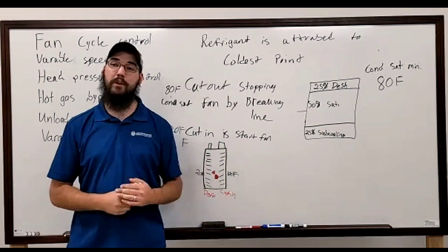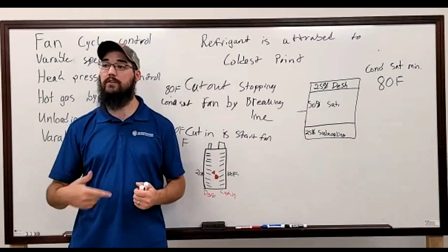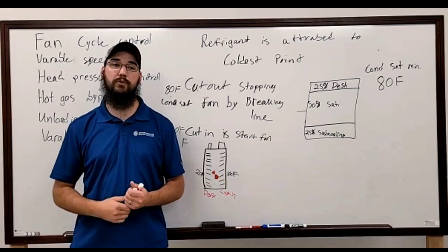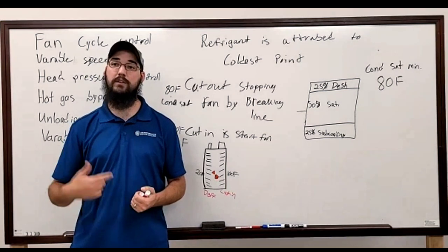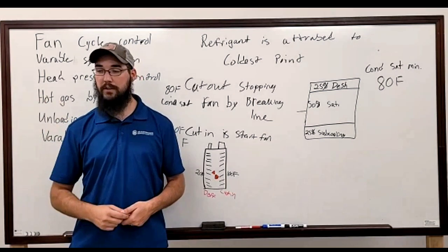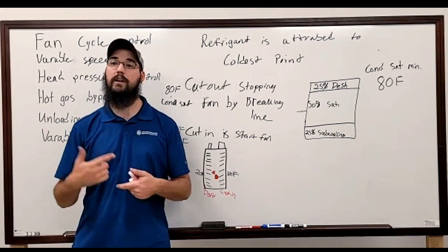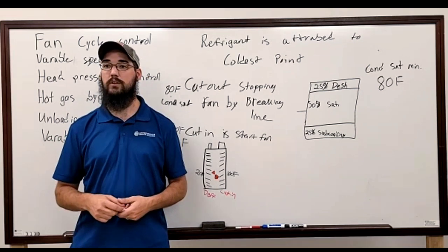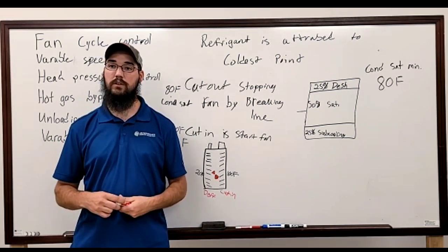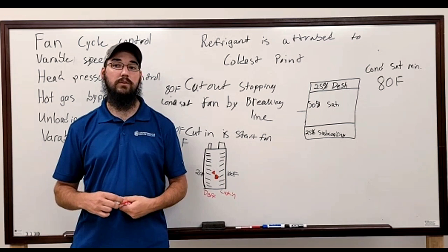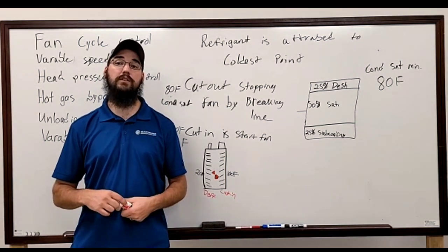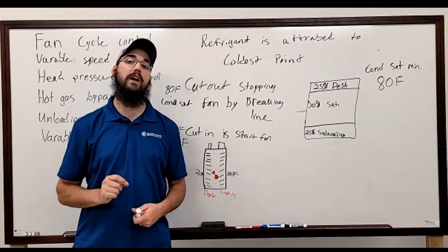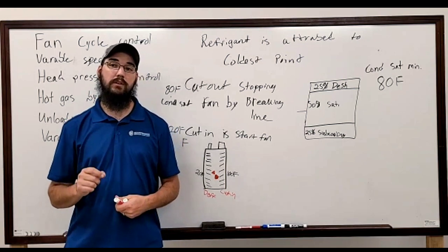Where that leads to is your heat pump will no longer function at all. You'll basically be running like a blower motor would do with no fan ever. It'll constantly freeze up. It'll be flooding the compressor routinely. You're going to have constant issues. This is in general, and this is on a very specific design of heat pump. Okay?